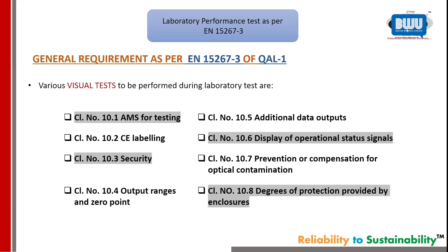So these are the tests. You remember that QAL 1, then 15267, 2, and 3. In 3, we have told you about the lab test and field test. Now in the lab test, these are the clauses. It has to be tested in the laboratory. It is called response time, repeatability, deviation at zero, at span, lack of fit, zero and span drift, influence of ambient temperature. Now see, I'll give you a beautiful example.